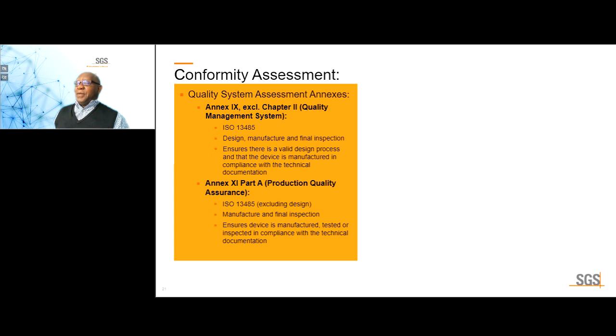So, as I indicated 2 slides before, there are 2 strands of evidence for conformity assessment. One is the quality assessment annexes, of which there are two. Annex 9, excluding Chapter 2, which is essentially based on ISO 13485, covers design, manufacture, and final inspection. It ensures that there is a valid design process and that the device is manufactured in compliance with the technical documentation. Remember, the technical documentation is the repository of all the information you are putting forward to the notified body to demonstrate compliance.